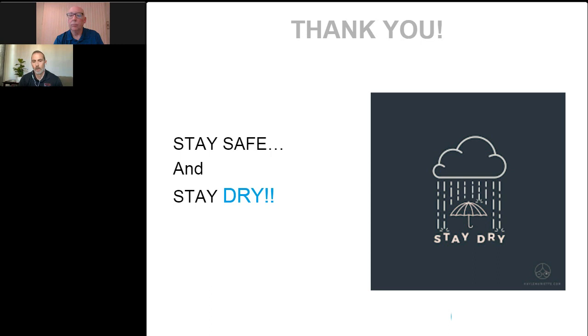Great point. So you mentioned IFUs, and there are IFUs out there that are not always very clear. What would your recommendations be for drying a device if it's not adequately specified in the IFU? So again, you want to take a look at the device itself and apply some of these basics, right? Lumens, it's the tubing technology. It can be quite sophisticated. It can be quite delicate as far as materials. So what you don't want to do is solely rely on compressed air, because the air pressure may be too much, right? So again, you want to work with your facilities folks if that's what you're using as compressed air to maybe turn down that pressure to allow that lumen to at least be blown out of water without causing any damage.